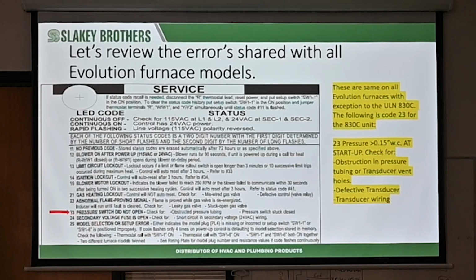Let's look at pressure switches. I think I got some schematics here for a pressure switch. So we're going to go from number 12. We're going to skip back and come back to these other ones because 13 and 33 go hand in hand. Before I go to 23, 24. They all share 24. Just means the fuse is open. On the circuit board, that little 3 amp fuse or 5 amp fuse, 24 just means the fuse is open.